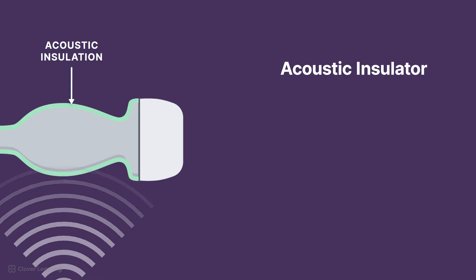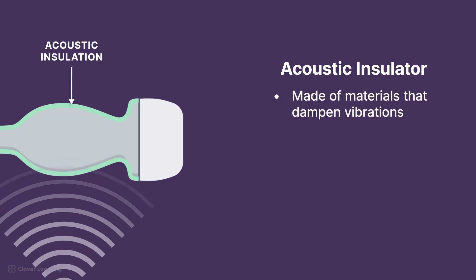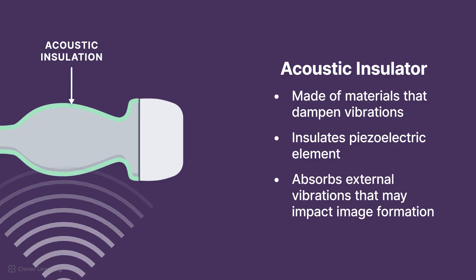Beneath the electrical shielding is the acoustic insulator. The acoustic insulator is made of materials that dampen vibrations, such as rubber-like polymers or foam-based materials, to insulate the piezoelectric element and to absorb any vibrations that may impact image formation.